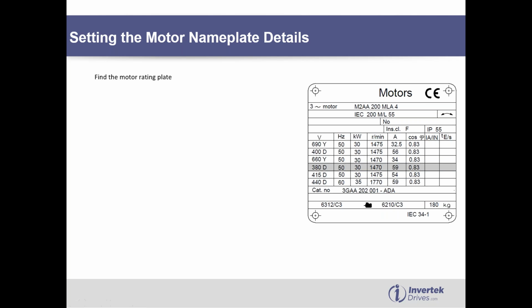So if we look at Jamaica, for example, that's 440 volt, 50 hertz. So here, that's 440 volt, 60 hertz, or we can use the 415 50 hertz. Either's fine. All we have to do is make sure we choose the closest one we've got there, and then the current rating for the drive. So if we think about this one here, we've got 440 volt. I know it's 60 hertz, but that's just the speed. We can sort that out easily enough. 440 volt, 59 amp.